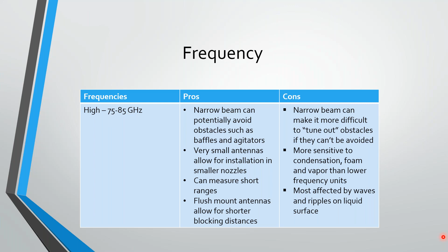So what are the pros and cons of non-contact radar? Well, just like guided wave, it's a direct level measurement as opposed to differential pressure or something like that. No moving parts, unaffected by density, viscosity, etc. With DP, if you put a different material in that tank that has a different density, you're going to have to retune that whole thing because it's not going to give you an accurate reading. Still fairly immune to dust, vapor, things like that, and we do get very high accuracy readings.